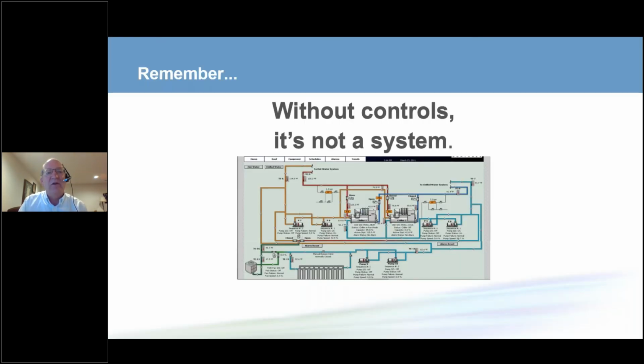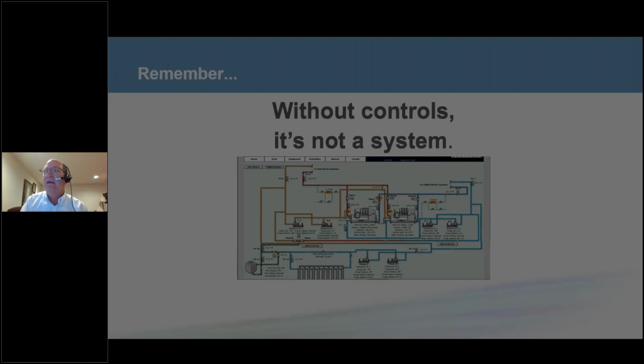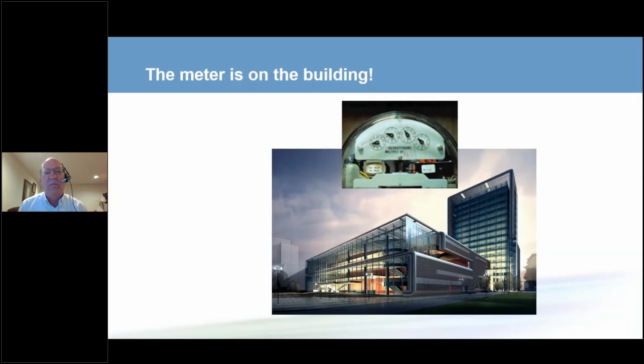First, again, without controls, it's not a system. It's just a bunch of different pieces trying to work, but there needs to be an integration. A chiller plant control system, a building automation system needs to coordinate and control the plant so we can make it simple, we can make it elegant, we can make it reliable and efficient. That's extremely important. Next, we always have to remember what the building owner pays for and basically what our impact on the environment is. As we reduce the energy usage of the system, of the building, we also reduce our emissions. We reduce the energy created at the power plant, the energy inputs to that power plant.